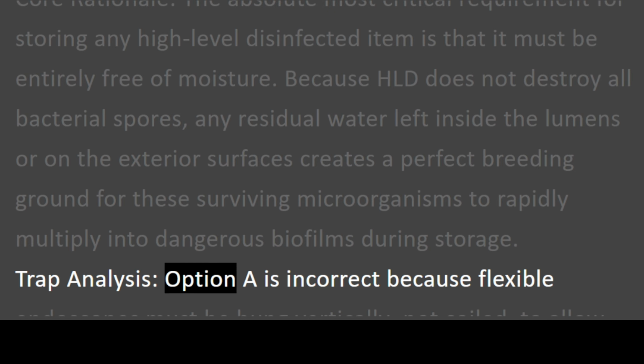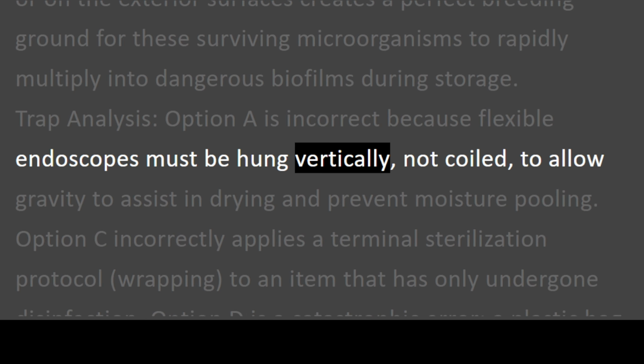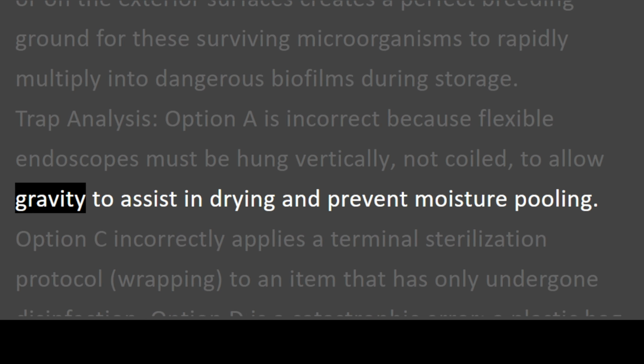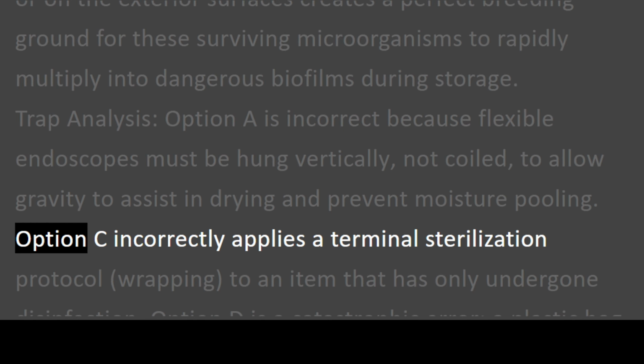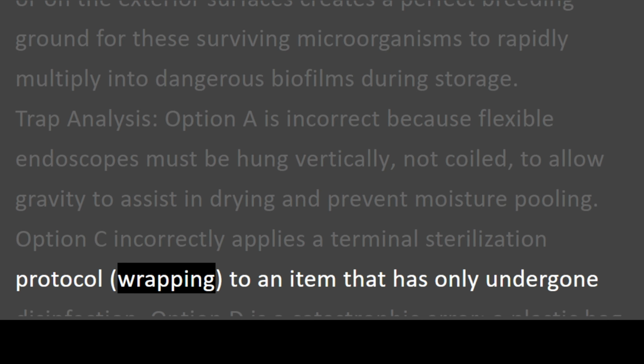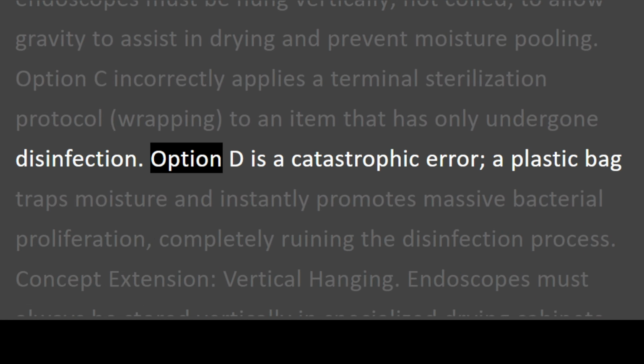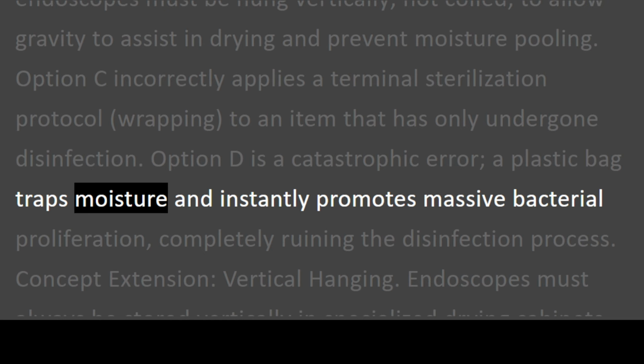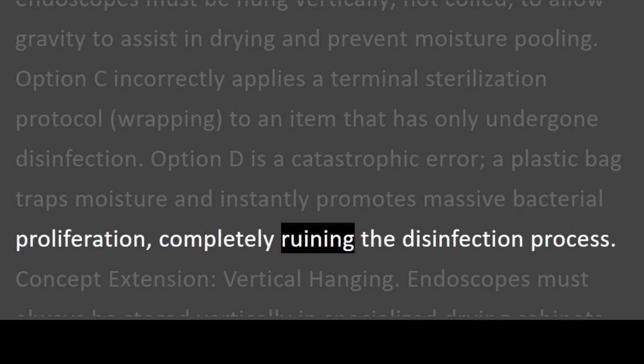Trap analysis. Option A is incorrect because flexible endoscopes must be hung vertically, not coiled, to allow gravity to assist in drying and prevent moisture pooling. Option C incorrectly applies a terminal sterilization protocol, wrapping, to an item that has only undergone disinfection. Option D is a catastrophic error. A plastic bag traps moisture and instantly promotes massive bacterial proliferation, completely ruining the disinfection process.